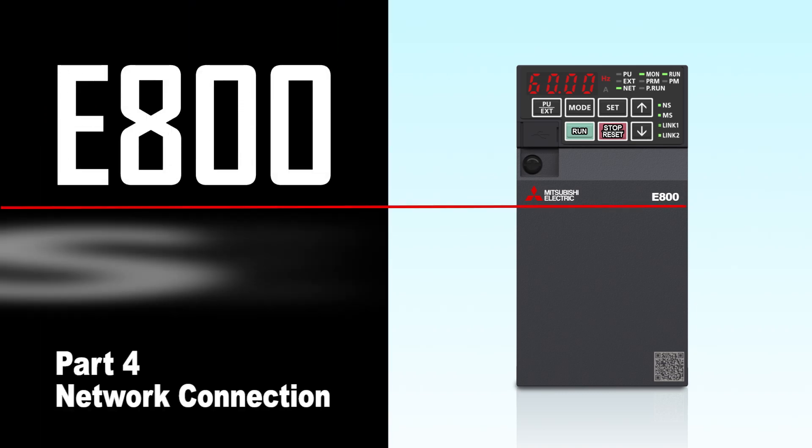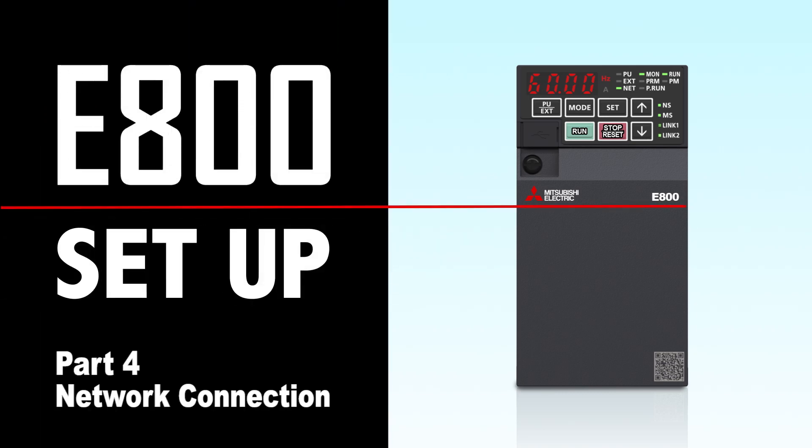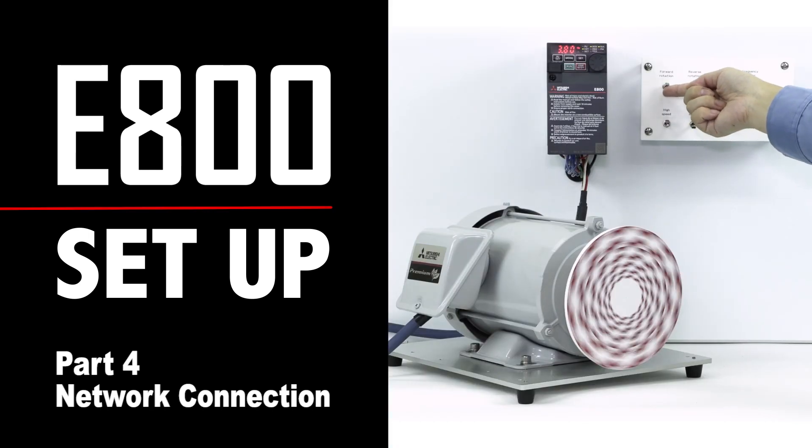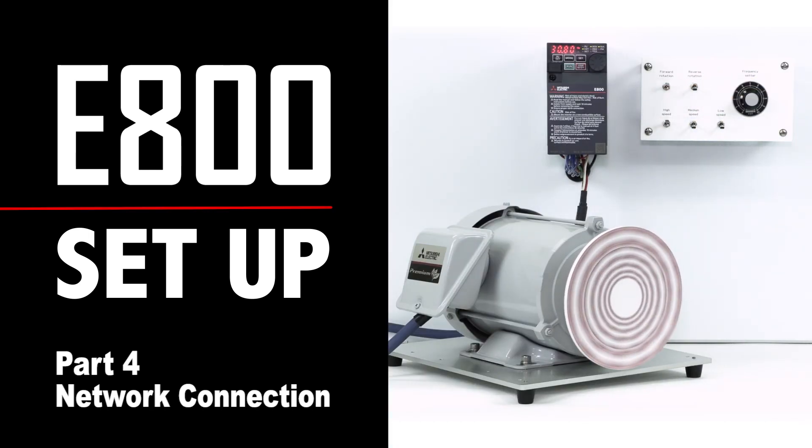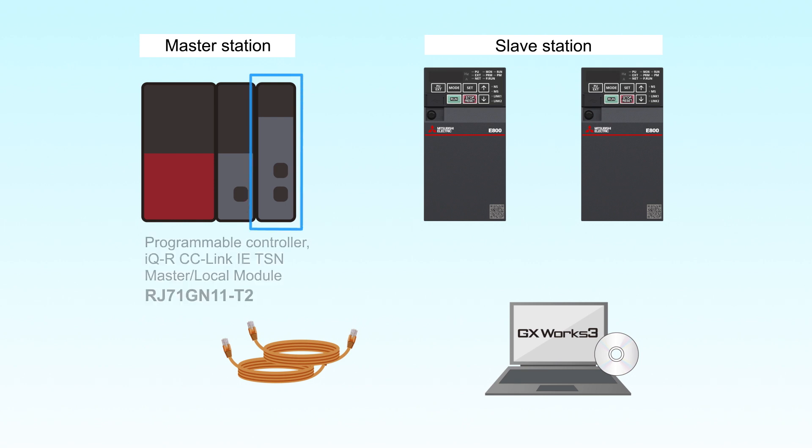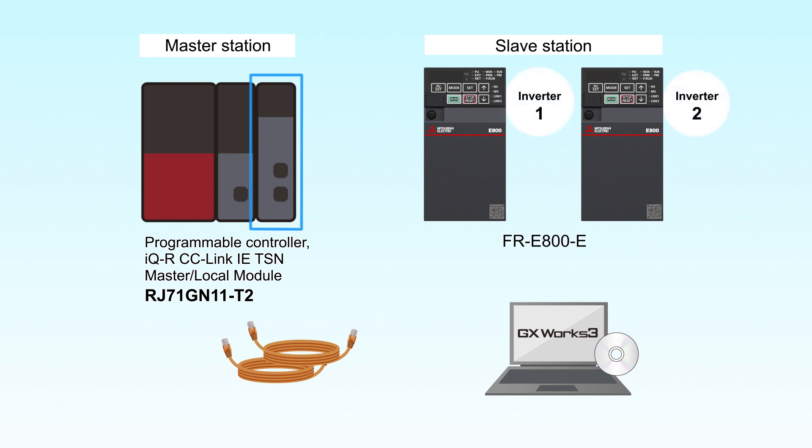We will now explain the settings for CC-Link IE-TSN communication using the Mitsubishi Electric FR-E800 inverter. The following devices are required: a programmable controller used as a master station containing an iQ-R CC-Link IE-TSN master local module RJ71GN11-T2, two FR-E800-E inverters used as the slave stations, Ethernet cables, and a computer installed with MELSOFT GX Works 3.